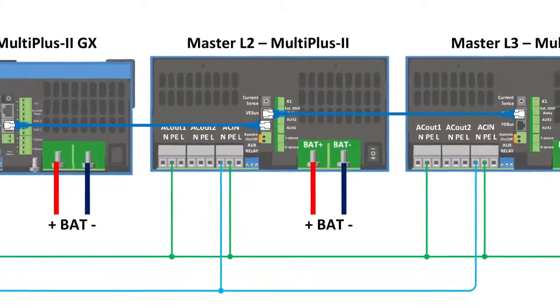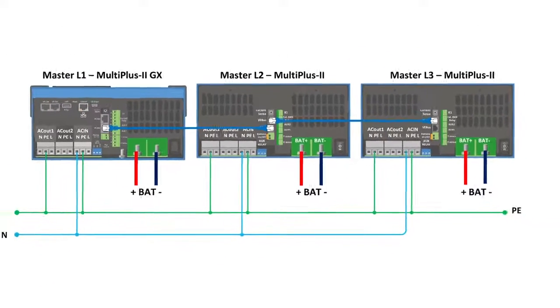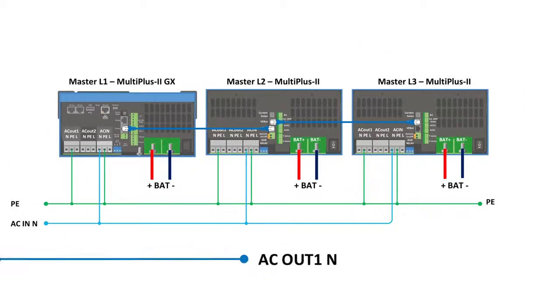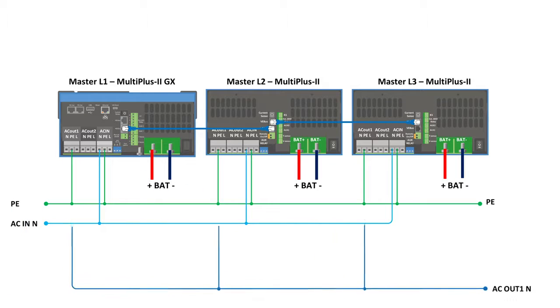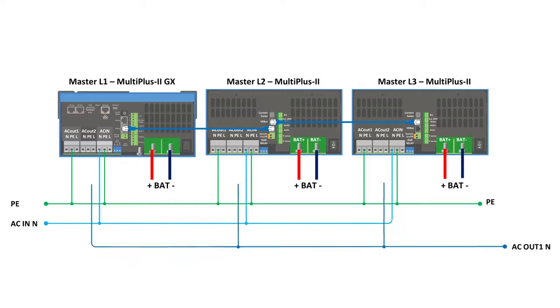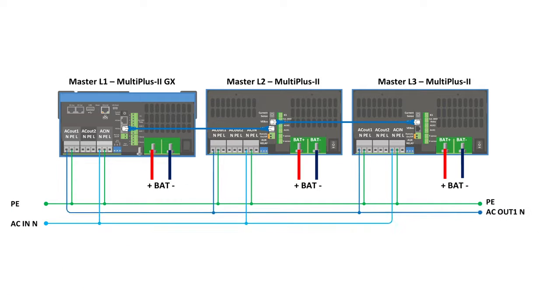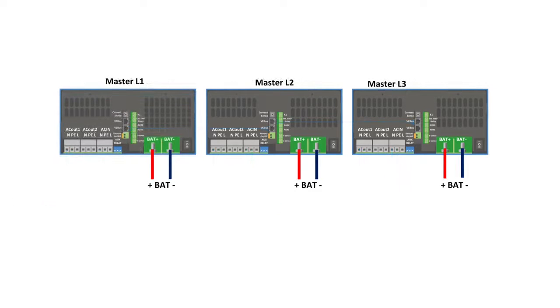For multi-phase systems, before switching these units on for programming, you need to link together the AC output neutrals of the multis. This guarantees the voltages between the multis have a common reference point. The 3-phase loads that run without neutrals also require this precise reference voltage. Once the AC output neutrals are linked, we can then go to the other AC wiring, although this is not essential to do before programming the units.